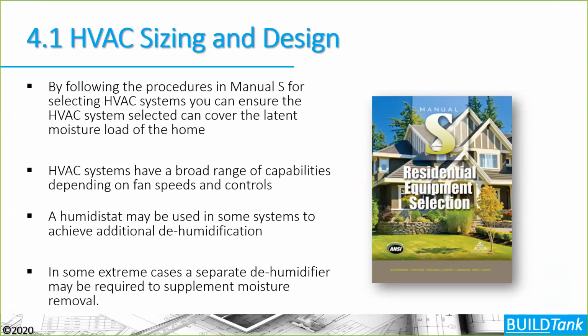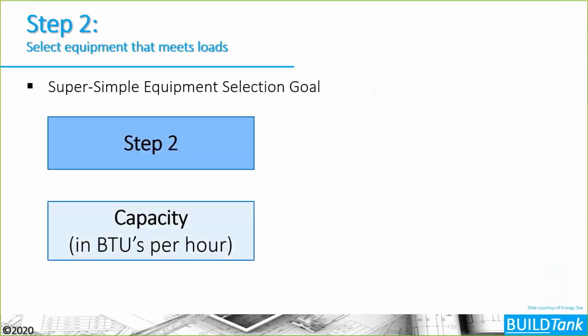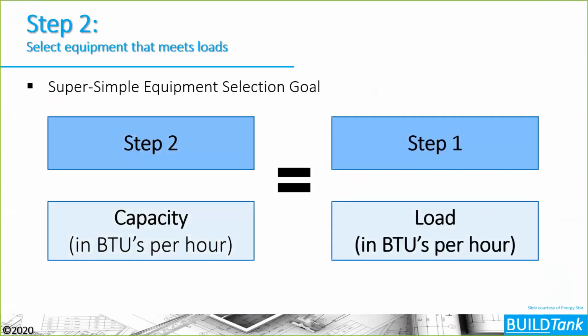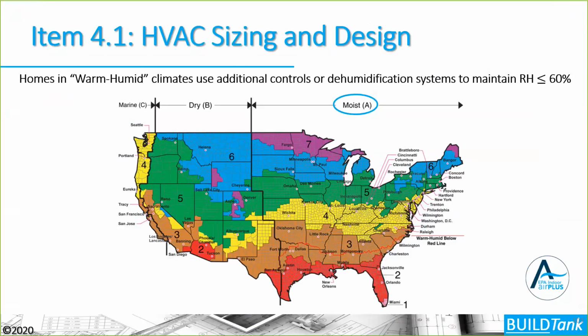So again, we have to follow Manual S here. Manual S is really trying to do something fairly simple here. It's trying to ensure that the capacity of our system is able to meet the load, that we have chosen the correct equipment, not only from a humidity perspective, which is the main reason why the program is trying to do that, but to make sure that we have good distribution of energy in our houses. We want our system to be right-sized, not oversized or undersized, so we're not short cycling or creating other issues in our HVAC systems in our houses.